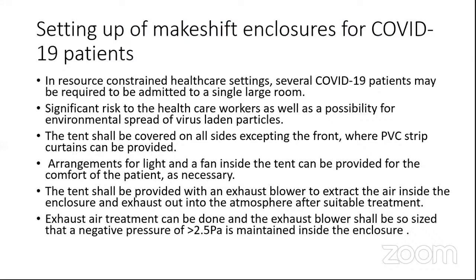Now, there are times when nobody is getting a bed, or some makeshift enclosures need to be made. If you're not getting a single room, then how do you go ahead with a makeshift enclosure? The tent should be covered on all sides with a PVC strip, and there needs to be a light and a fan. If possible, the tent should have an exhaust blower, or rather it is recommended that it has an exhaust blower to extract the air from inside the enclosure. A negative pressure of more than 2.5 pascals needs to be maintained in the enclosure, because that makes all the difference. If this is not maintained, it would contaminate the other areas in and around that enclosure.